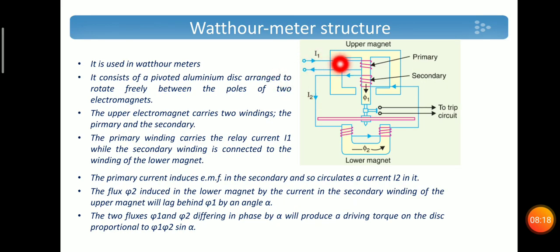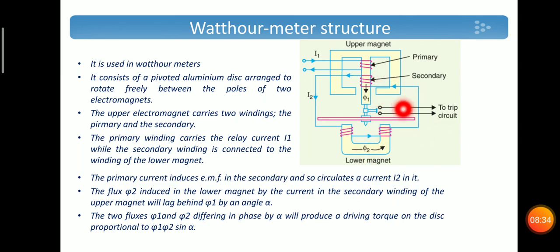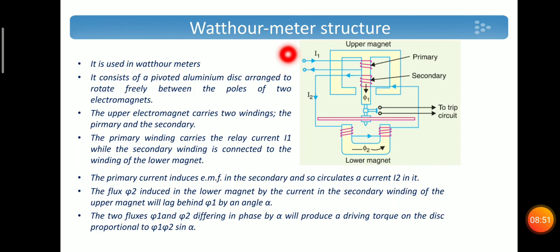The next type is the watt-hour meter structure, used in watt-hour meters. It consists of a pivoted aluminum disc arranged to rotate freely between the poles of two electromagnets. The upper magnet carries two windings — the primary and secondary. The primary winding carries the relay current I1, while the secondary winding is connected to the lower magnet. I1 is the current in the apparatus to be protected, and due to that current, a current I2 is induced in the secondary winding, which also flows through the lower electromagnet.